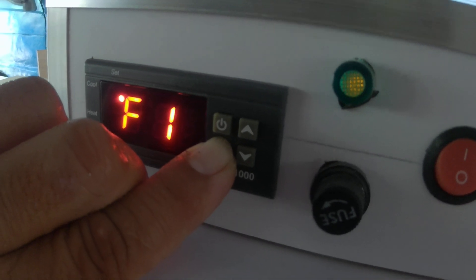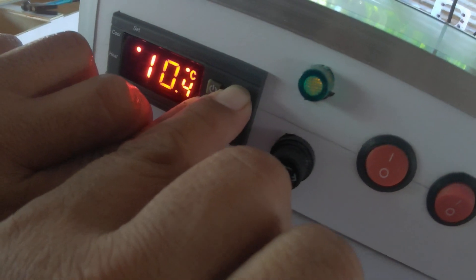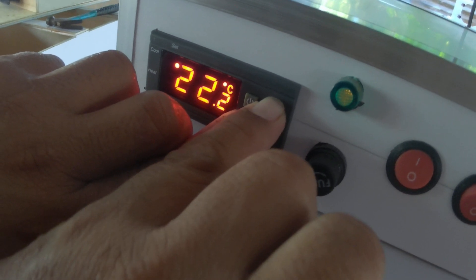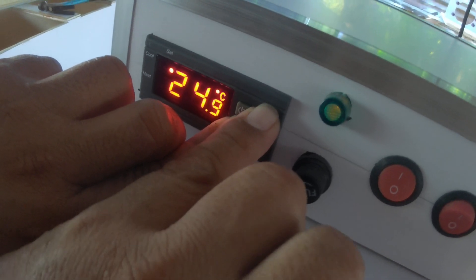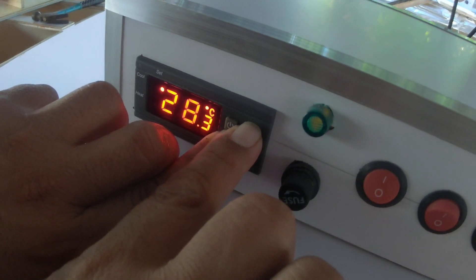Let's set this thermostat. Press and hold the S button for almost 3 seconds, wait for F1 to show, then hold and press the upper button to set this to 37.8. Long press the S button, wait for F1 to show, then press again and press one by one up to 37.8.